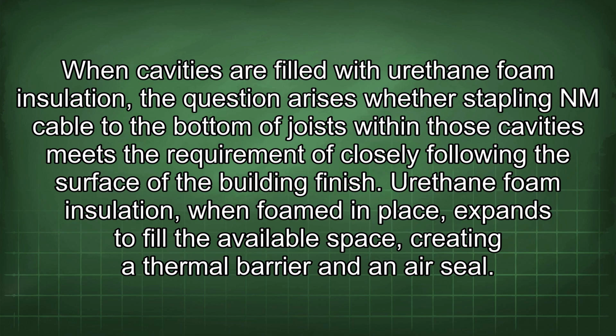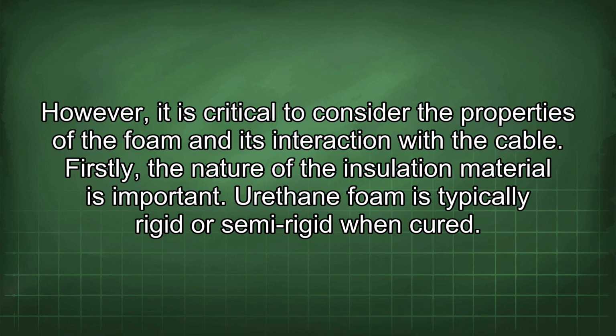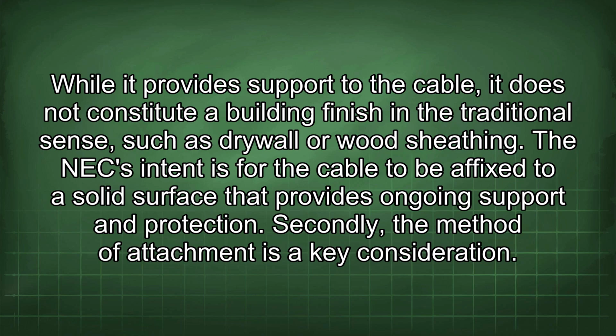Urethane foam insulation, when foamed in place, expands to fill the available space, creating a thermal barrier and an air seal. However, it is critical to consider the properties of the foam and its interaction with the cable. Firstly, the nature of the insulation material is important. Urethane foam is typically rigid or semi-rigid when cured. While it provides support to the cable, it does not constitute a building finish in the traditional sense, such as drywall or wood sheathing. The NEC intent is for the cable to be affixed to a solid surface that provides ongoing support and protection.